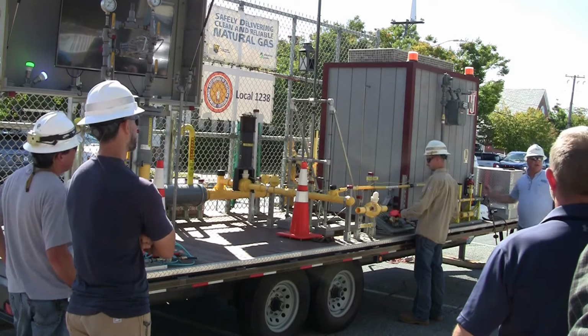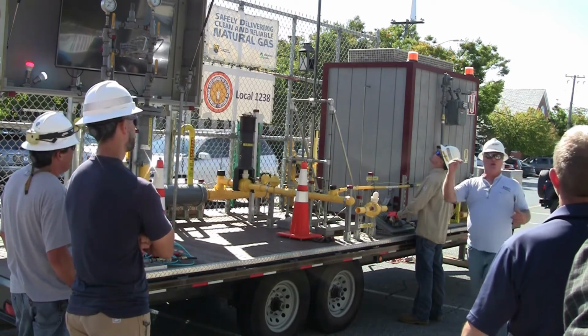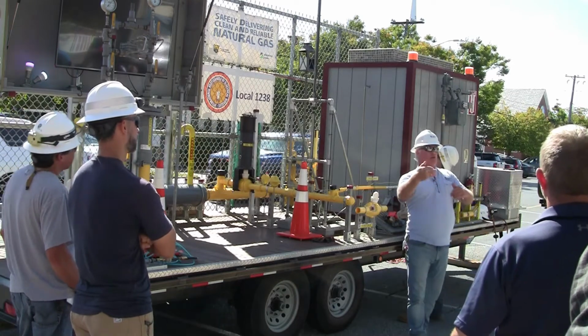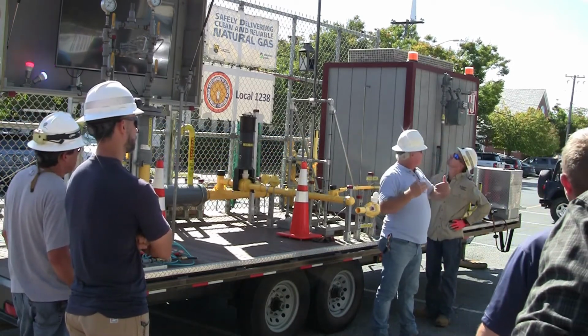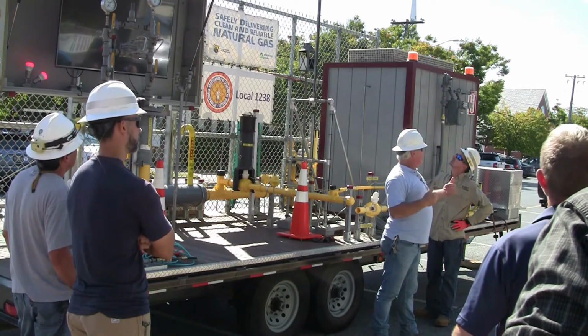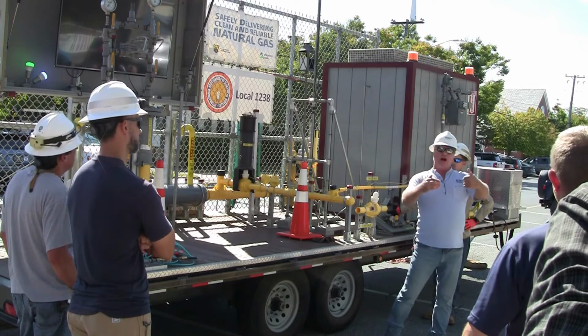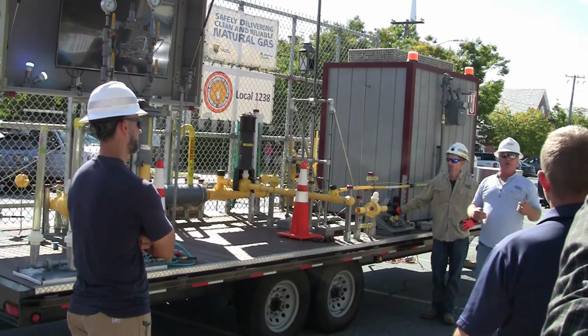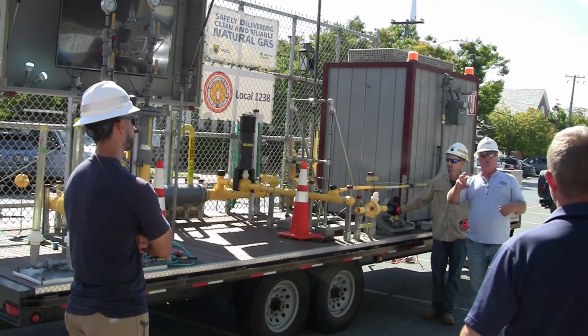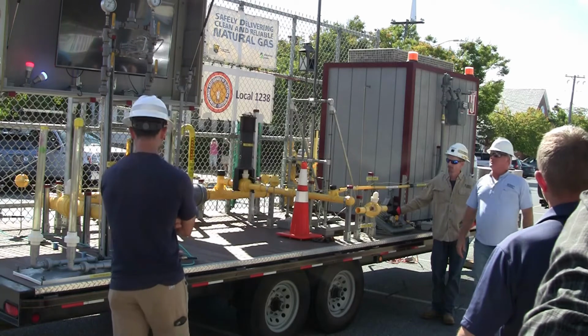So this represents residual gas coming first. We're trying to pack the line because we're bringing actual natural gas. We want to get to at least 99% natural gas. So we're packing the line, we're pushing it, and over a mile long takes a little while, probably about 3-4 hours, because we're opening the valves very slowly and just introducing gas into the system.